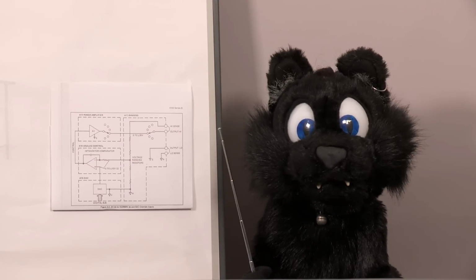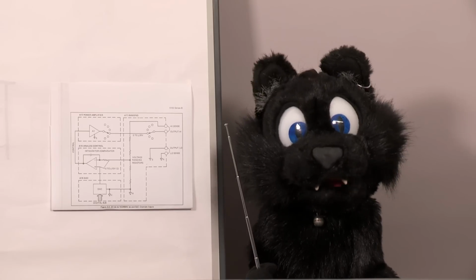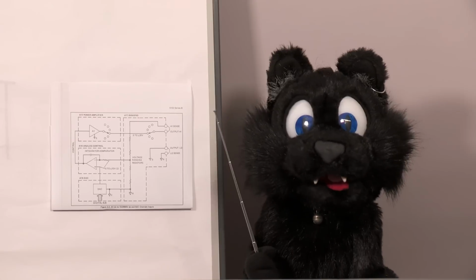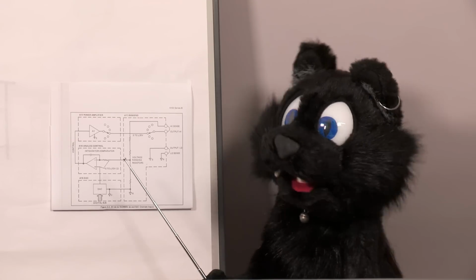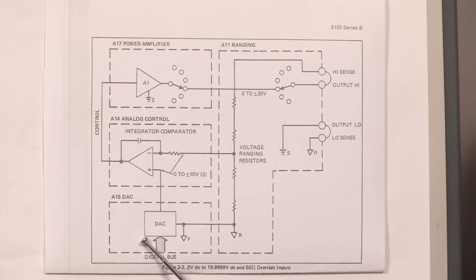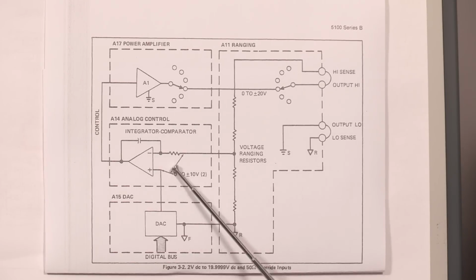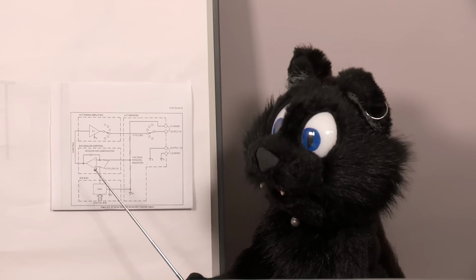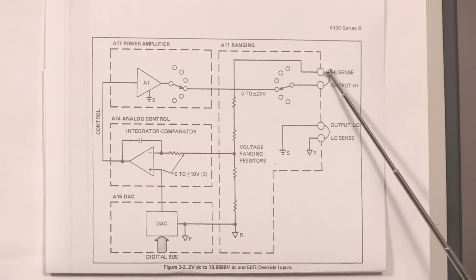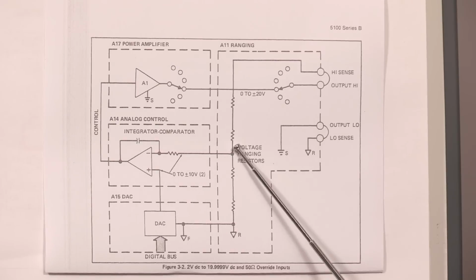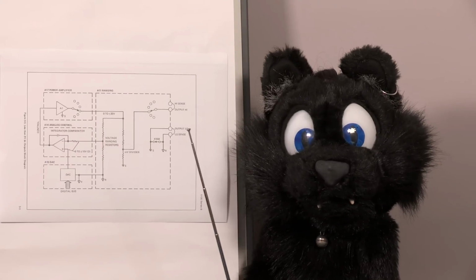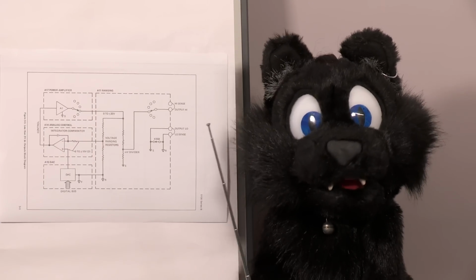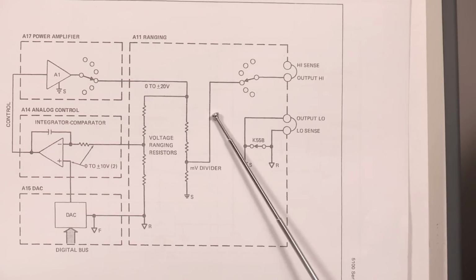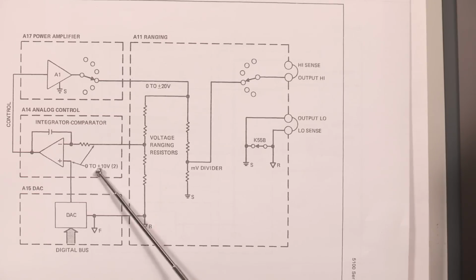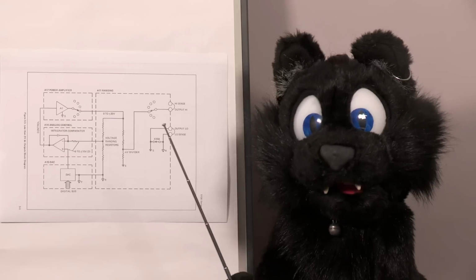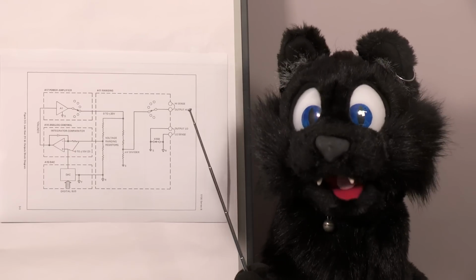The low range DC, all below 20 volts, which is the point where my unit is supposed to fail, is done with this configuration. The numeric value that is requested as an output is set from the digital analog converter as a reference voltage, the output of which goes through the power amplifier to the output and back via the sensing lines and a divider network for the control loop. Voltages below 2 volts have a separate precision divider so that the regulated control voltage is still in the 0 to 10 volt range. Note that this can't use the sense lines because their feedback would be off by orders of magnitude.